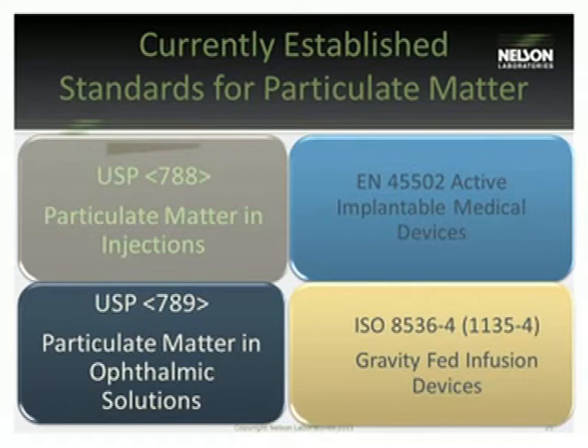But if your device does fit into one of those two, or there's a couple others that exist, there's an AT6 1996 that's for, I can't remember the exact device. That's for recollecting blood during internal bleeding, basically auto transfusion devices. That's what they're called. So this is why you should put everything on your PowerPoint. But most devices do not have a standard, as I discussed earlier, and so we'll get on later into how to set limits for those devices.